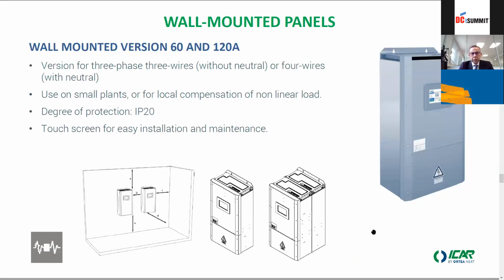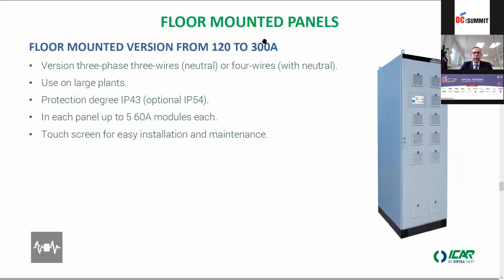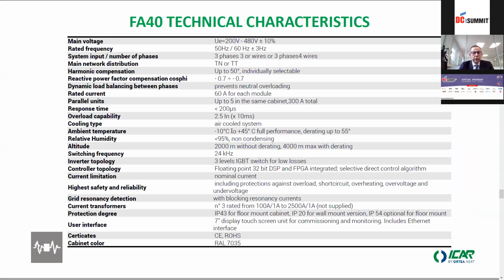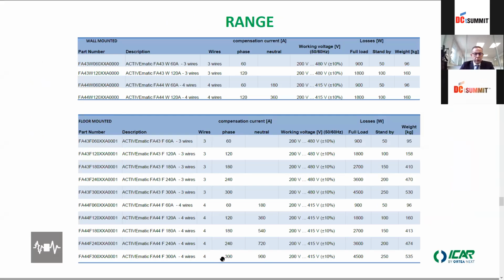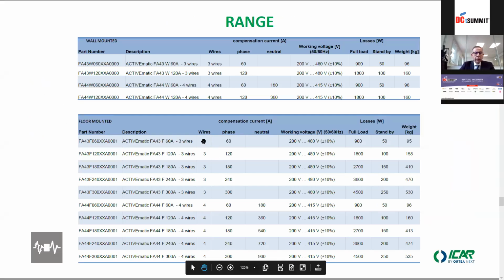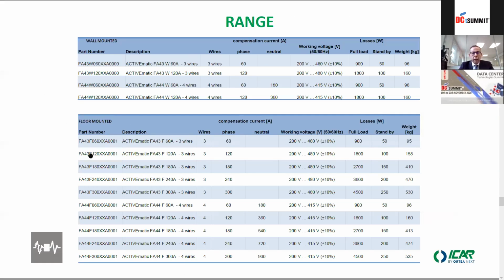We have different configurations, which can be floor-mounted or wall-mounted. We do reach 300 amps, and units can also be put in parallel to increase the power, with different IP levels, with neutral or without neutral, depending on the installation, if it's only 3-phase or 3-phase plus neutral. These are some characteristics of the active filters. So this is the range, up to 300 amperes with 4 wires, so 3-phase plus neutral, or only 3 wires, wall-mounted units or floor-mounted units. So it depends on the type of installation.